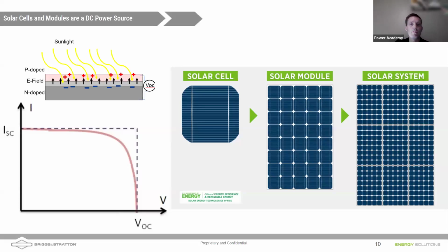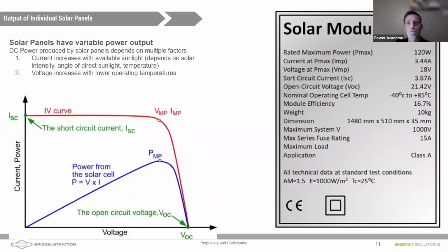And I've seen that in the home solar array that I had in my house. That's one of the arguments that companies like Enphase with microinverters or SolarEdge with optimizers make about using their optimizers or their microinverters. They say in shaded conditions, microinverters and optimized string inverters are more efficient, and that can be true. So if shading is a common thing, AC coupling with microinverters might be a better option for the solar array.